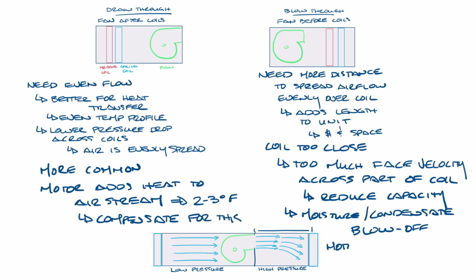The fan will also add heat to the airstream in a blow-through arrangement, but it'll actually warm up the air before it gets to the cooling coil, so you don't have to worry about it going to the space, but you will have to account for a higher entering air temperature on your coils. So that's the difference between blow-through and draw-through configurations.